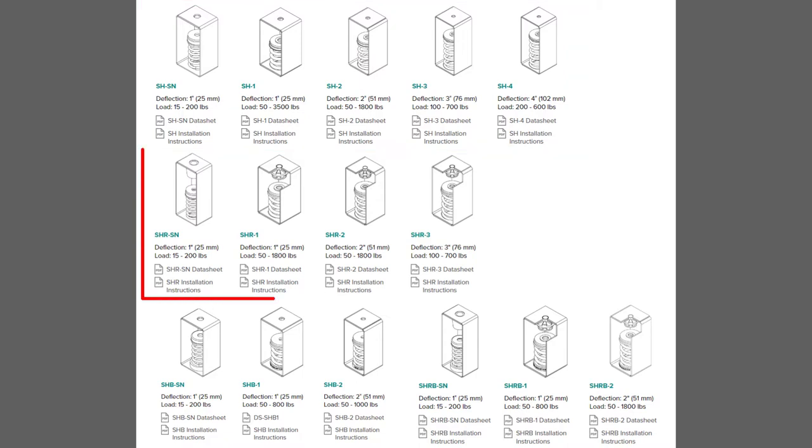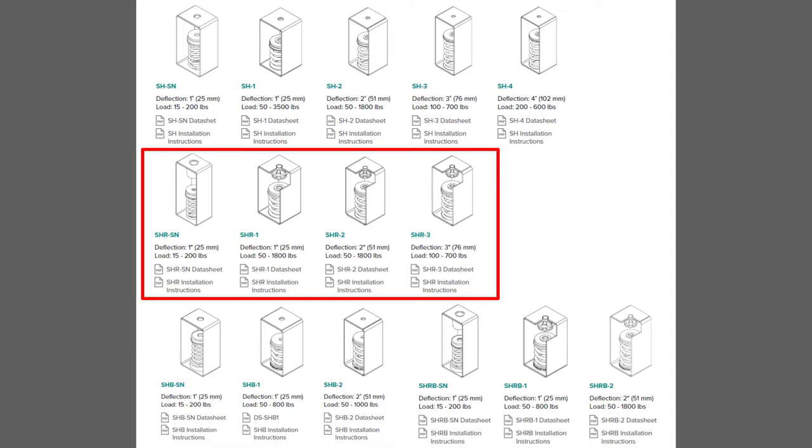The next group are the same as the SH versions but with an additional rubber element at the top of the box. This is probably the most popular spring hanger version since it is the most cost-effective product that provides isolation across a broad range of frequencies. There is no SHR-4 at this time since the box isn't tall enough to accommodate both.